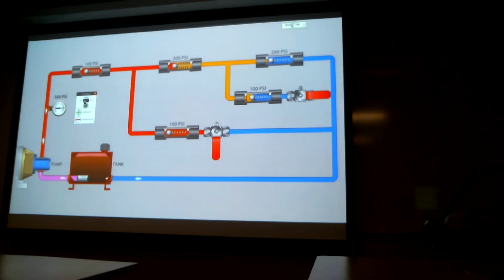Here we go. Aha, 500 psi. Congratulations to you if you got that right. Our new path of least resistance, given the closed shutoff valve, is through the 100 psi check valve, then this 300, then this 100.